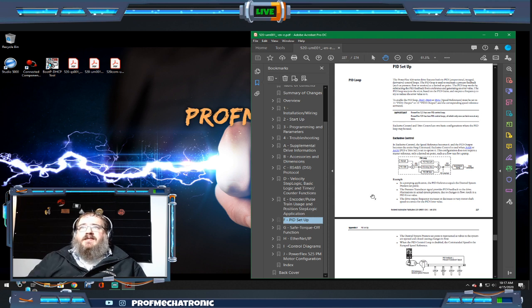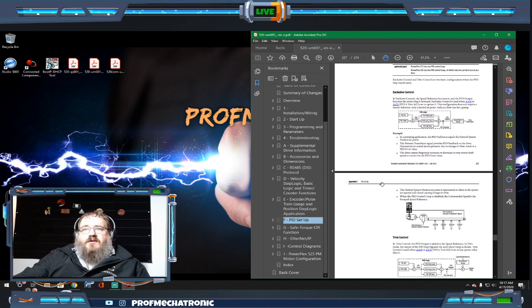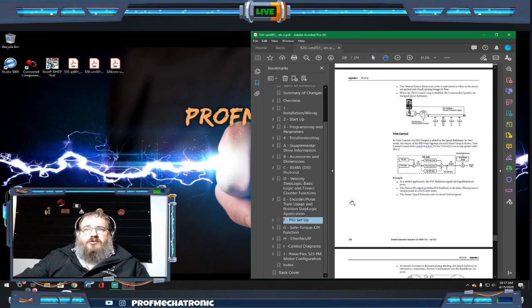We can also do PIDs, proportional integral derivative control, inside of this drive itself instead of being in the PLC. The PLC and exclusive or specialized controllers are a little bit better at doing that, so I'd suggest still doing that on that side rather than worrying so much about putting it into the drive. But understand that if you need some kind of standalone system, this drive can do a lot of this control itself.